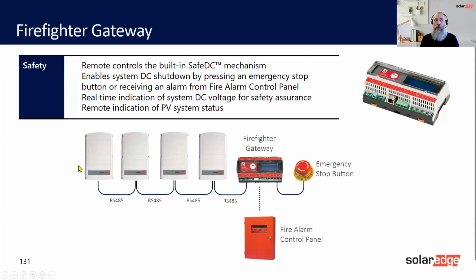One of the most common things we get is people calling us saying, "Oh, we did a fire alarm test the other day, and none of the inverters have come back on." And we say that's perfect, because it's exactly what it should do. It shouldn't come back on until you've reset the device. Okay, so that does its job. This is just a link between emergency stop and a fire alarm to get them to do it.